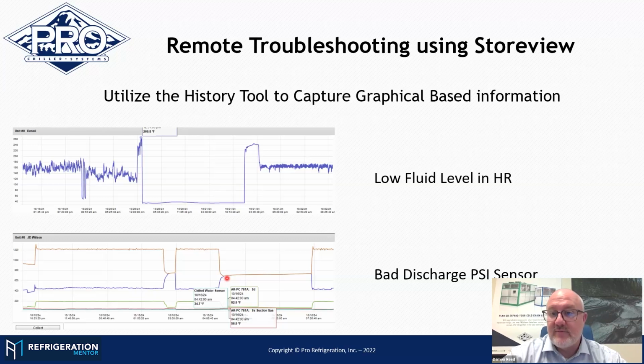It just wasn't reading accurately. So that you can verify, that's when you make that call to get on site. But the remote diagnostics kind of already pointed the direction, like, hey, we're going off on high pressure or low pressure. Let's make sure those pressure transducers are reading accurately. So on-site time was 20 minutes, super quick to get it identified.